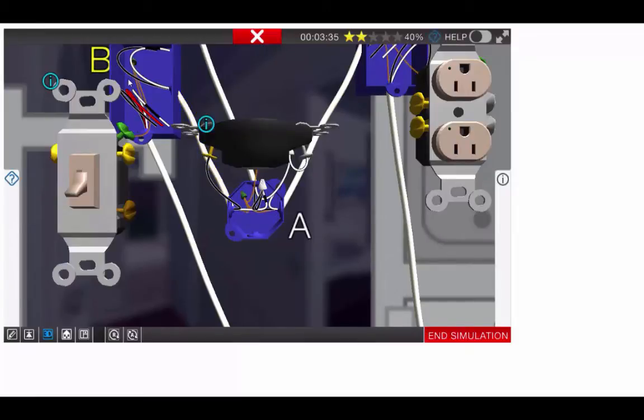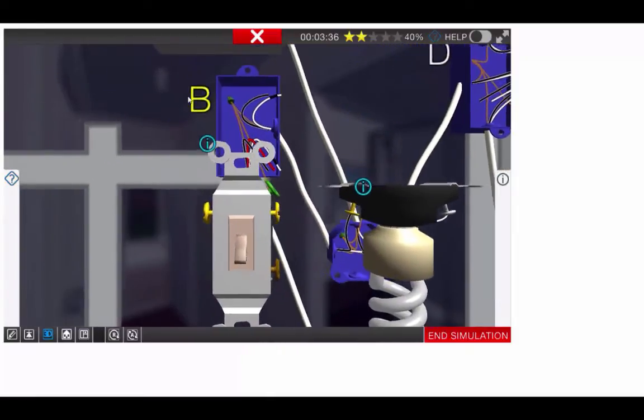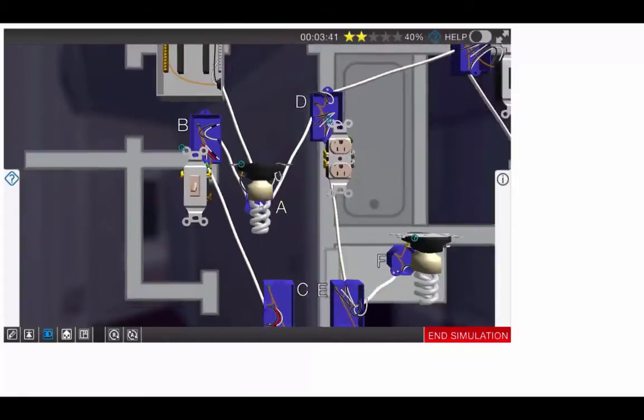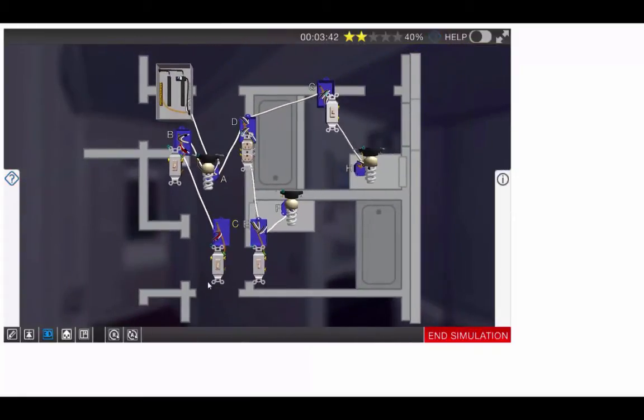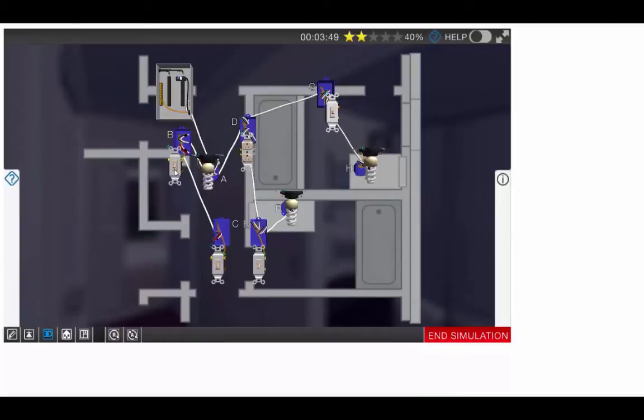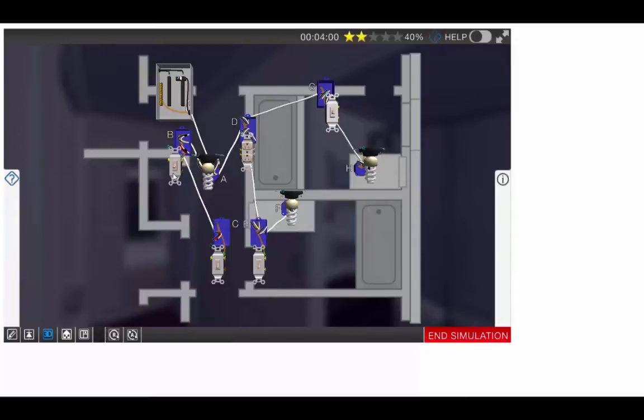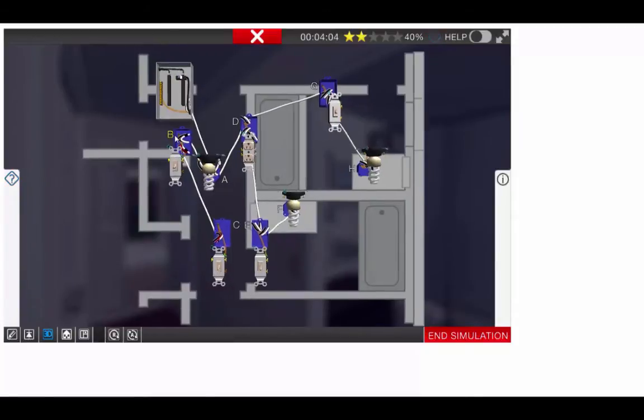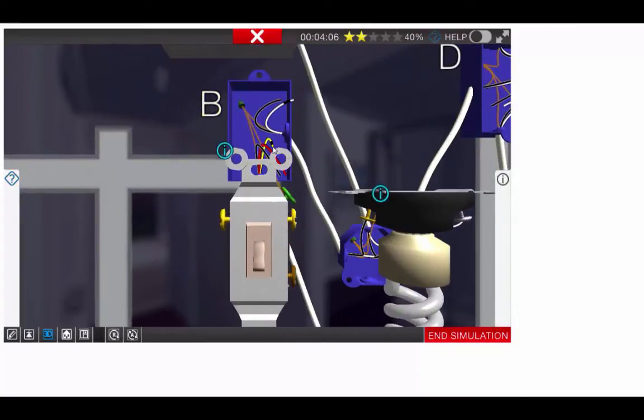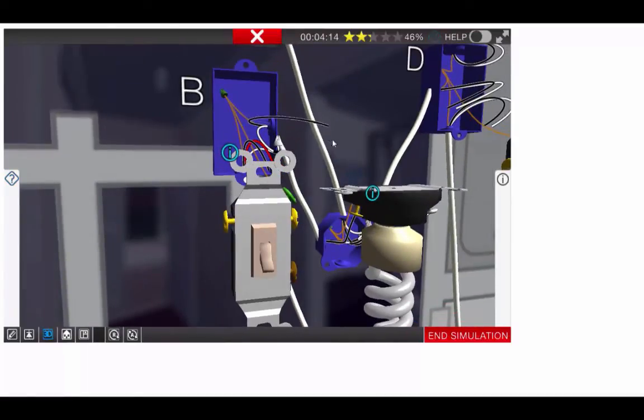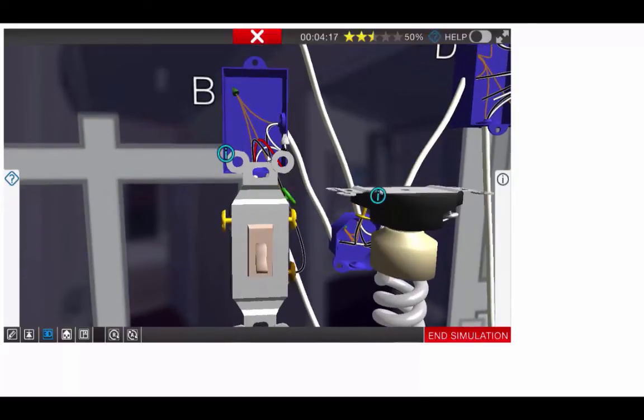Now we'll move to box B. As we talked about before, the hot will be going down to the switch C. On a 3-way circuit, one switch needs to be the switch leg going to the device. The other switch will be the hot coming from the panel. In this case, box C will be our hot from the panel, and box B will house our switch for the switch leg. So we'll start in box B. We'll hook up our hots. Remember, we re-identified those with black tape. We'll have our travelers go into our switch.